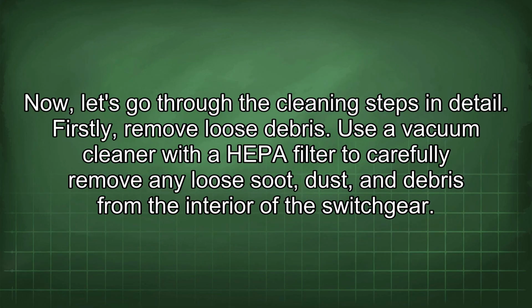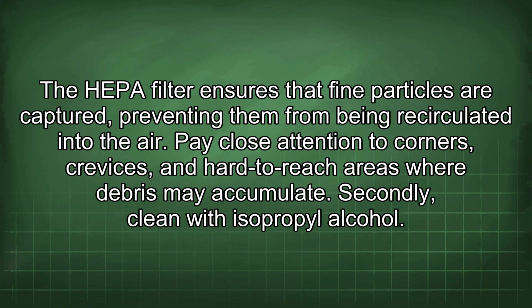Now let's go through the cleaning steps in detail. Firstly, remove loose debris. Use a vacuum cleaner with a HEPA filter to carefully remove any loose soot, dust, and debris from the interior of the switchgear. The HEPA filter ensures that fine particles are captured, preventing them from being recirculated into the air. Pay close attention to corners, crevices, and hard-to-reach areas where debris may accumulate.